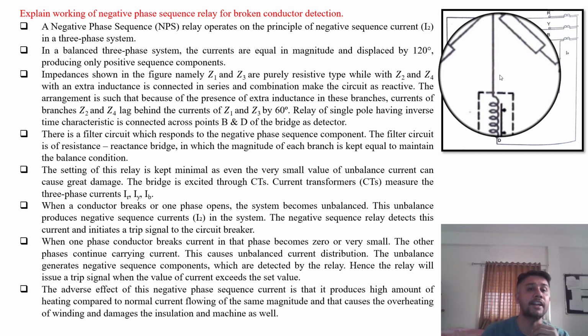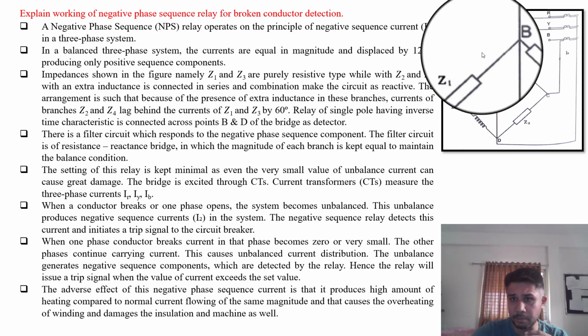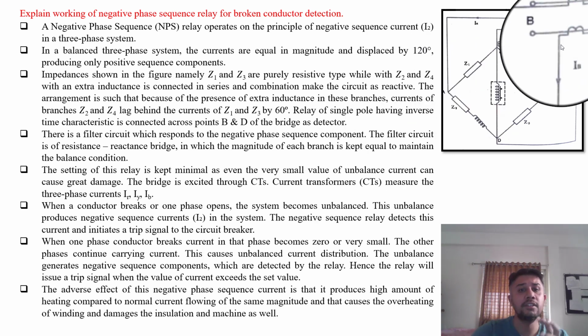There is a filter circuit which responds to the negative phase sequence component. The filter circuit is a resistance-reactance bridge in which the magnitude of each branch is kept equal to maintain the balance condition. The setting of this relay is kept minimal, as even a very small value of unbalanced current can cause great damage. This bridge is excited with the help of current transformers, CTs.